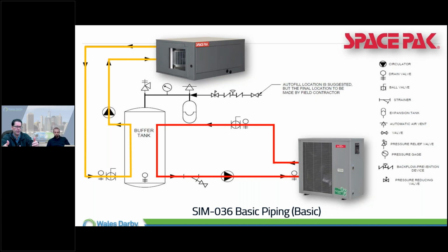You're going to consider redundancy, as we said before, same as with the DX refrigerant heat pump outdoor unit - still running off R410A currently. So it's only going to give you a certain amount of BTUs cooling and heating, and in heating it will dwindle. You need to know where it doesn't carry the load anymore, because we only have certain sizes available, and now we might need redundancy or backup.